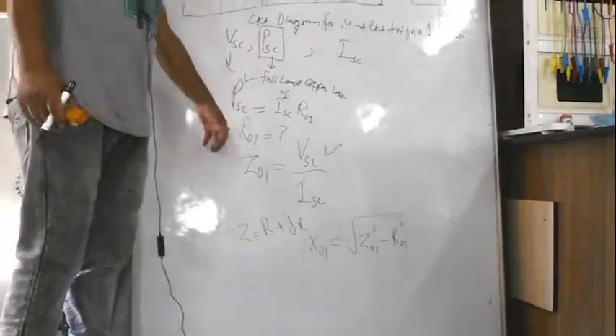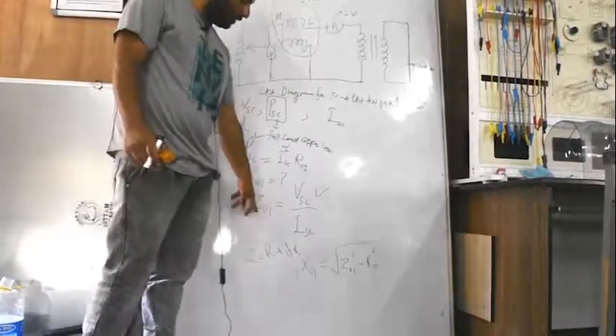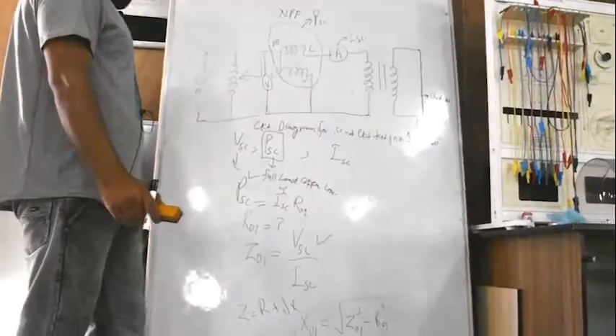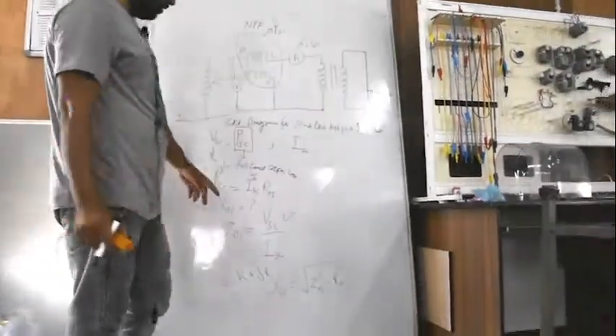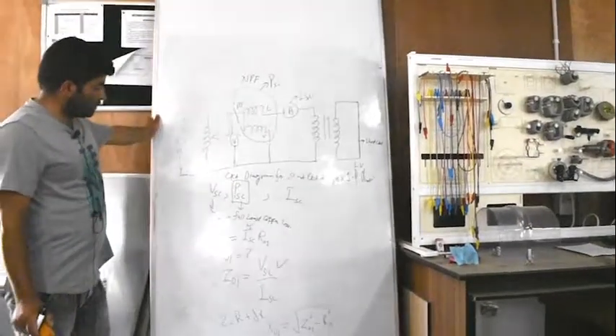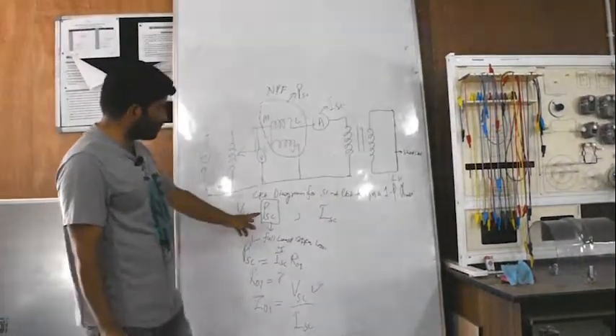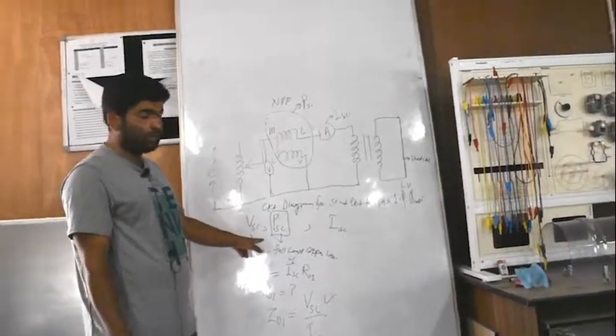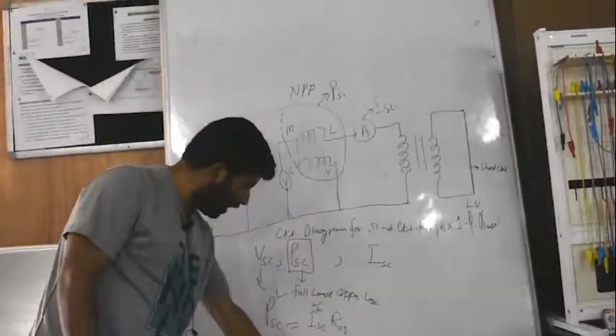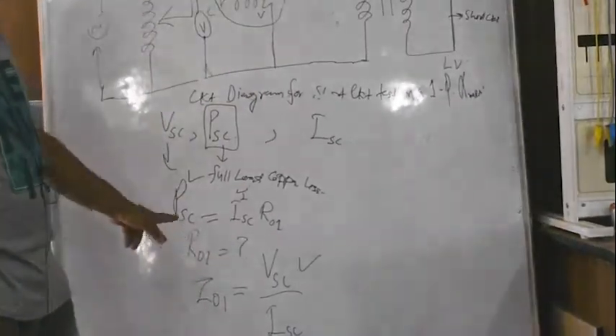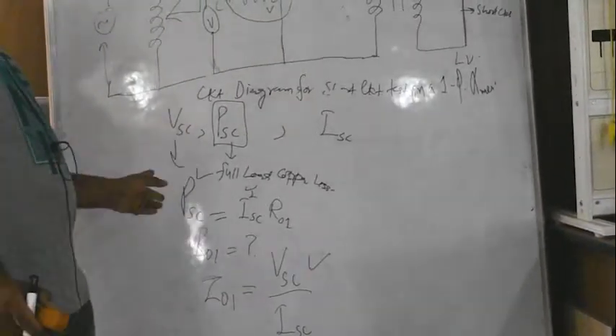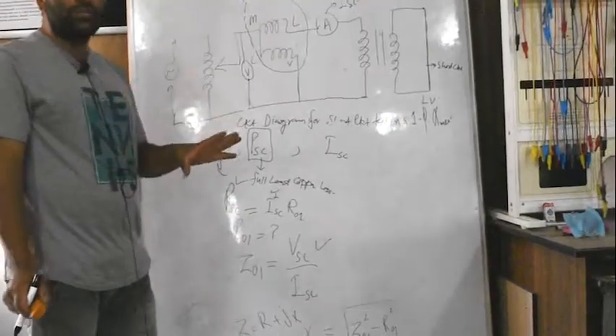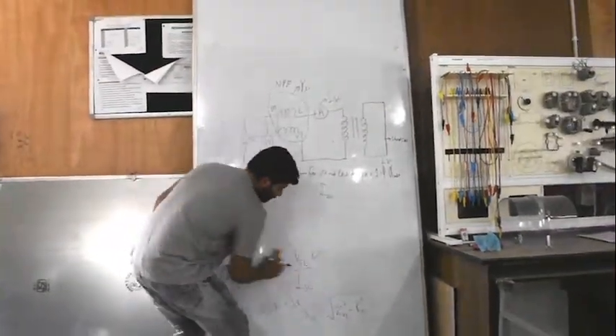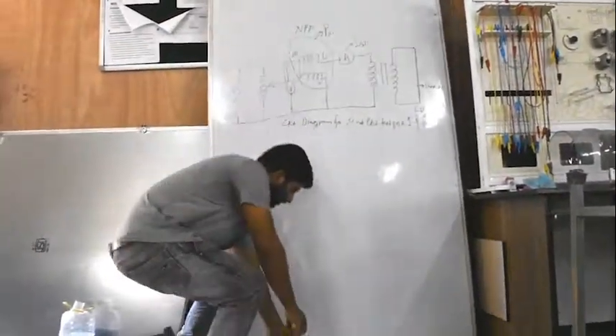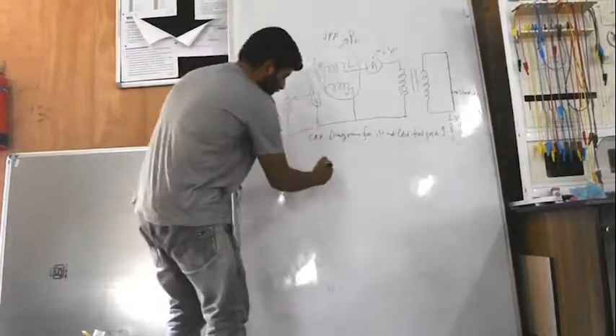So first we calculate the resistance as referred to the side from which you are performing the experiment. Then you obtain the equivalent impedance, and from that data you can calculate the equivalent reactance X01, right? So by performing the short circuit test, what you have obtained is the voltage at which the short circuit current is flowing, and the parameters R01, X01 and Z01. Knowing all these parameters from the short circuit test, plus the other parameters from the previously performed open circuit test, we can frame the overall equivalent circuit like this.